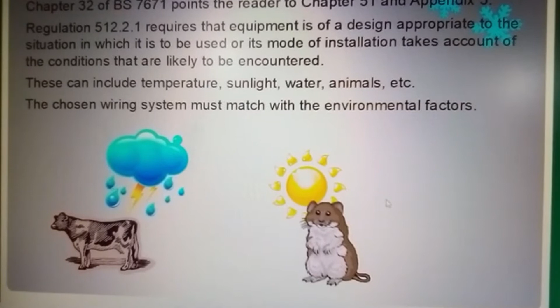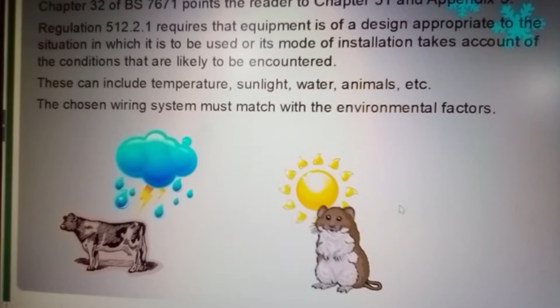Now, Chapter 32 of BS 7671 points the reader to Chapter 51 and Appendix 5. Regulation 512.2.1 requires that equipment is of a design appropriate to the situation in which it is to be used, or that its mode of installation takes account of the conditions likely to be encountered. These can include temperature, sunlight, water, animals, etc. The chosen wiring system must match the environmental factors.